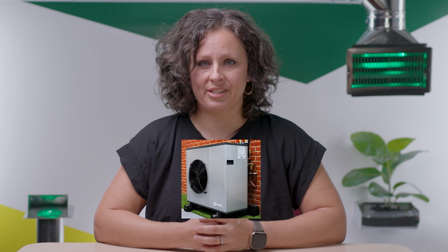Having the right sized heat pump is important, and here's why. Oversized heat pumps: if your heat pump is too big, your unit could short cycle a lot, which can cut down the lifespan of your heat pump dramatically and cause more frequent repairs. You'll also have uneven heating throughout your home and an increased energy bill. Undersized heat pumps: if your heat pump is too small, you'll have similar energy and repair problems but with different causes. Since your unit will be overworking, it will have long run cycles, which will shorten your unit's lifespan and lead to more repairs. You'll also have poor heating throughout your home and higher energy usage. In either case, you'll be stuck with an uncomfortable home, a high energy bill, and a broken heat pump.